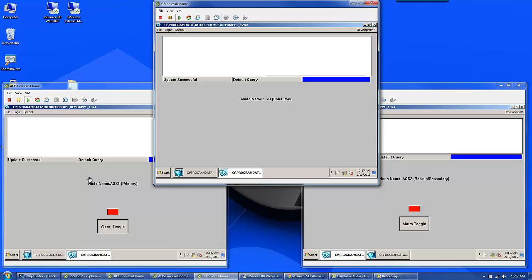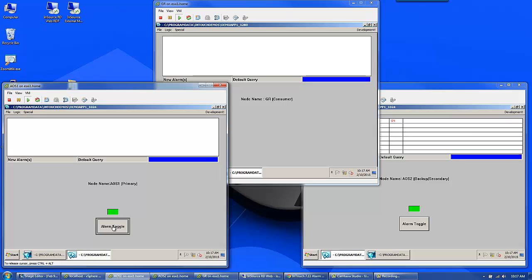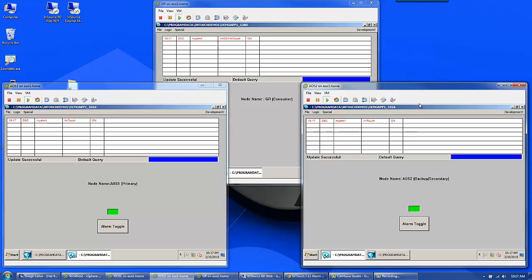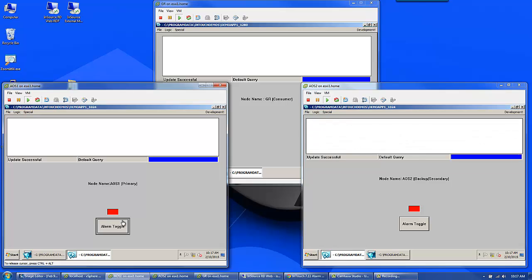So let's see what that looks like. Let's generate an alarm. If I go down to AOS1 and toggle an alarm, you see that I get the alarm in all three places. I can acknowledge from any one of the three locations. The consumer is looking to the pair that's synchronizing between the two. I'll come over here and acknowledge — acknowledgement gets sent everywhere. We'll clear the alarm.